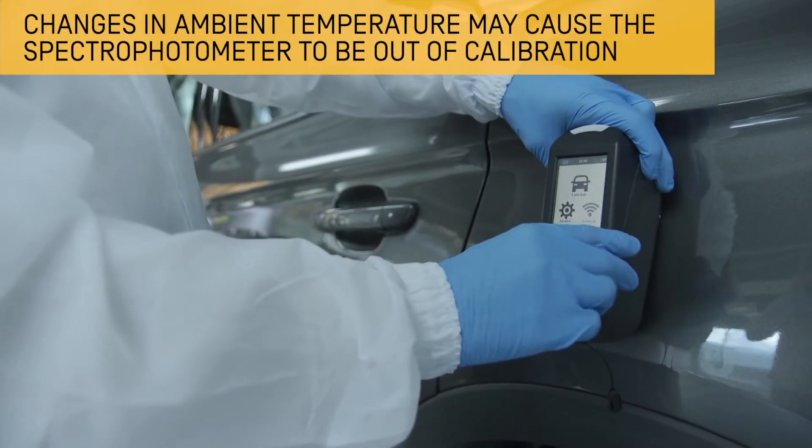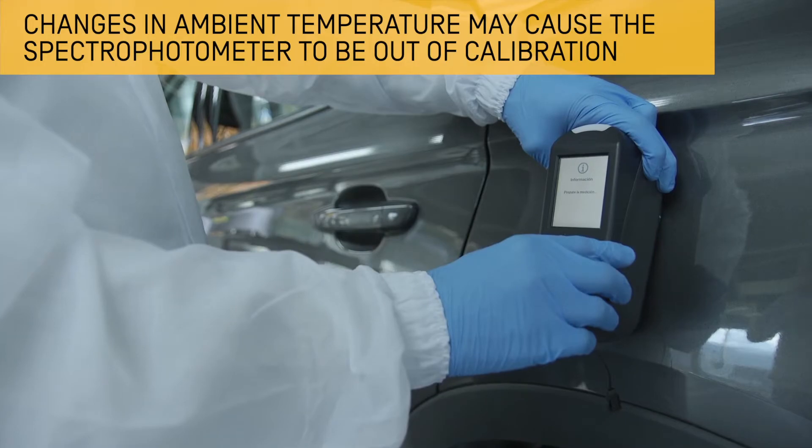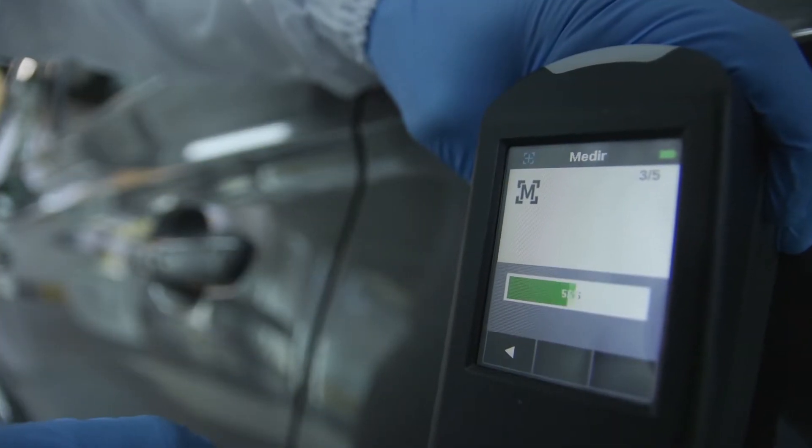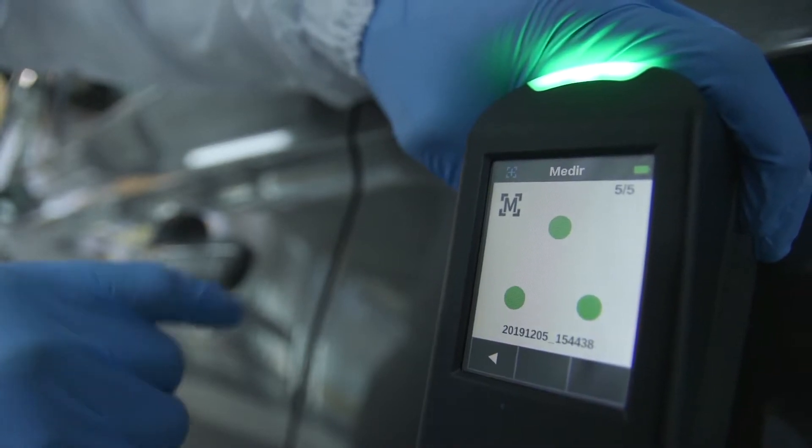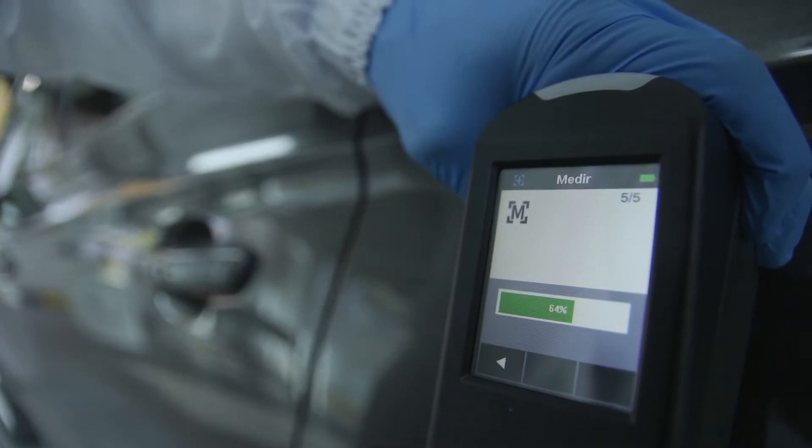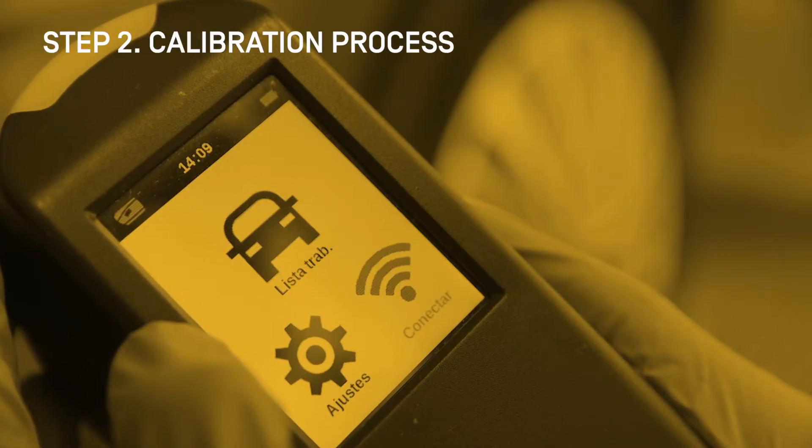Be aware that the spectrophotometer can get out of calibration due to sudden changes in ambient temperature. According to the manufacturer's instructions, the calibration process should be carried out at least every 14 days. Our recommendation is to do it on a daily basis, as the time required is minimal in relation to its benefits.